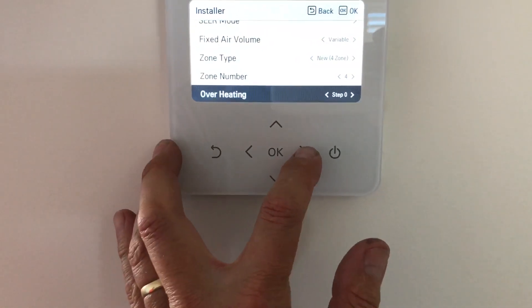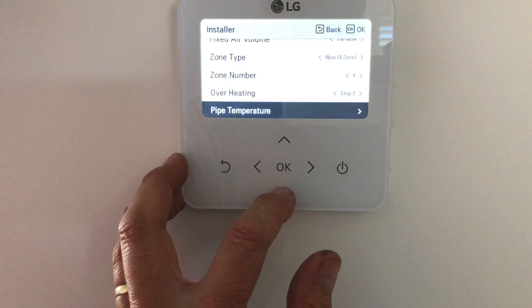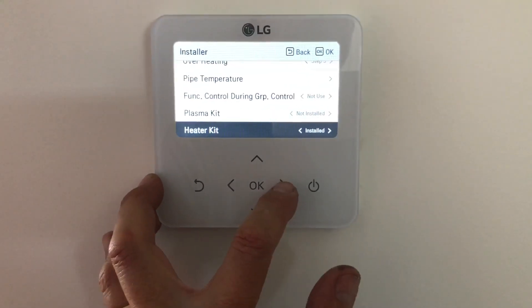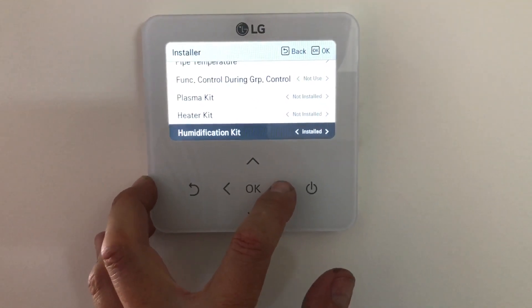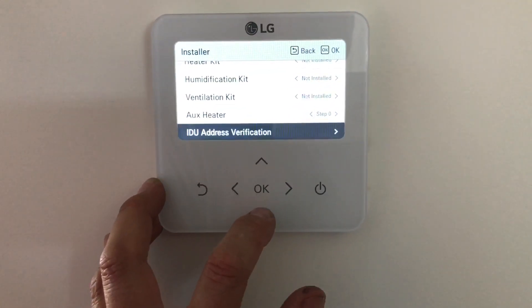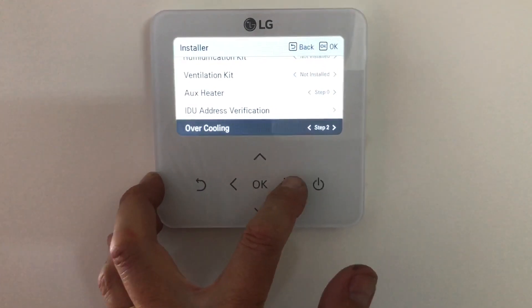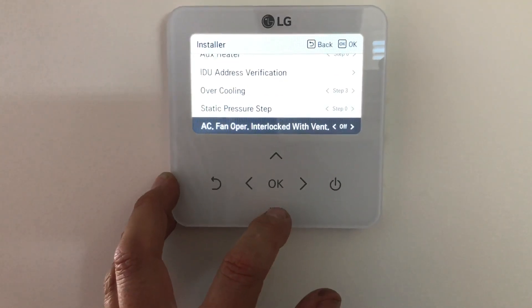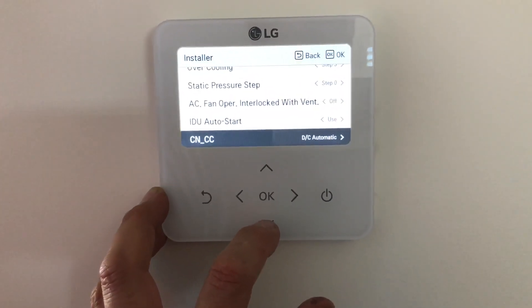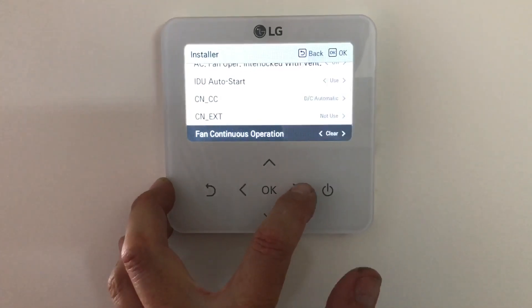Another setting to set is overheating — set that to three steps. That just brings the proportional band in closer and keeps a tighter temperature. Pipe temperature just shows you the temperature of the pipe — not used. Plasma kit — not installed. Heater kit — not installed. Humidification kit — not installed. Ventilation kit — not installed. Auxiliary heater — not installed. Overcooling — that's another important one to change to keep a closer set point, just change it to step number three. Static pressure — leave that as is. Fan interlock off. Indoor unit auto start — this means it'll automatically start if it was on before and the power goes off. Fan continuous — clear. Clear means that the fan will cycle off along with the thermostat.